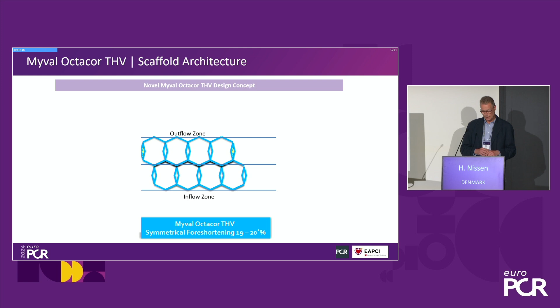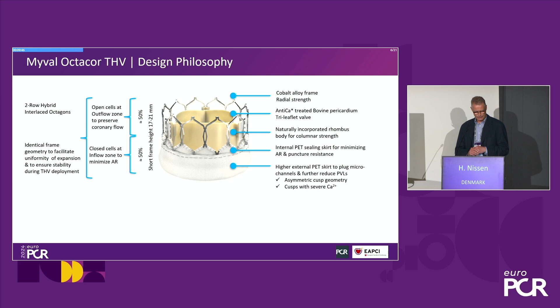It has an open cell structure, which gives ample access to coronaries. Its lower half has closed cells, of course, to mitigate the PVL, and then it has an external skirt, which both mitigates the PVL and also helps if hostile calcium or other material could impede the valve function. It's a cobalt alloy frame with a good radial strength, and it has a proprietary anti-calcium treatment from the company. And this external skirt allows good accommodation to calcified annuli.